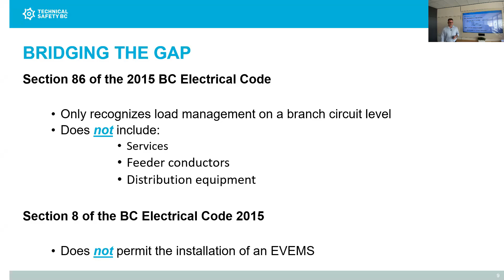In the 24th edition of the 2018 Canadian Electrical Code, EVEMS shall be recognized, defined as the control of electric vehicle supply equipment loads through the process of connecting, disconnecting, increasing, or reducing electric power to electric vehicle supply equipment and the connected electric vehicle. At this time, in order to bridge the gap, Technical Safety BC will consider applications for a variance of Section 8 and Section 86 of the BC Electrical Code 2015 for installation of an EVEMS until 2018 adoption. As for 2018 adoption, it's presently under regulatory review, and until such time, a variance application process will be needed to recognize any new changes from the 2015 BC Electrical Code.